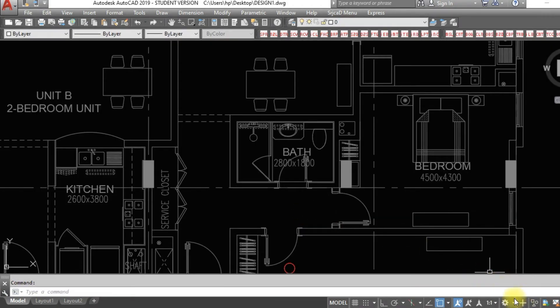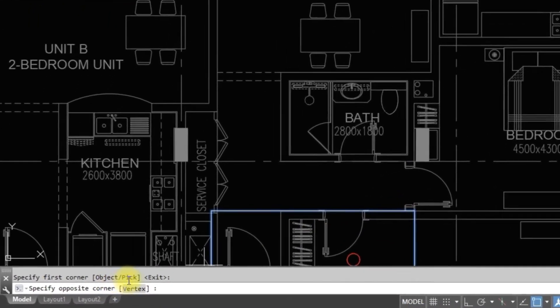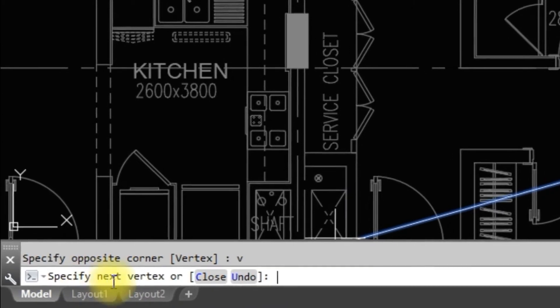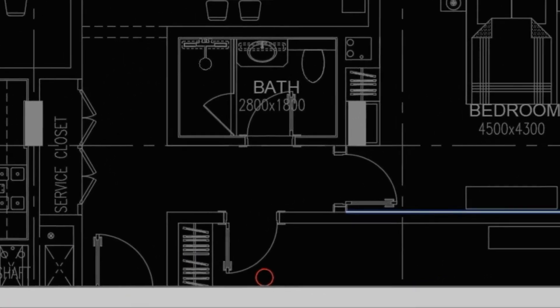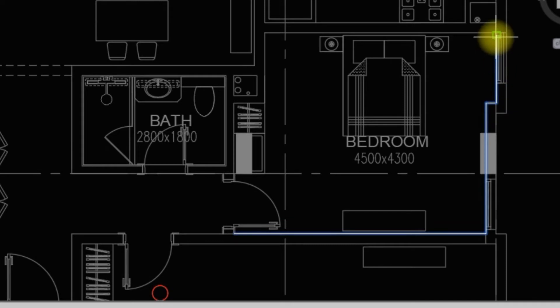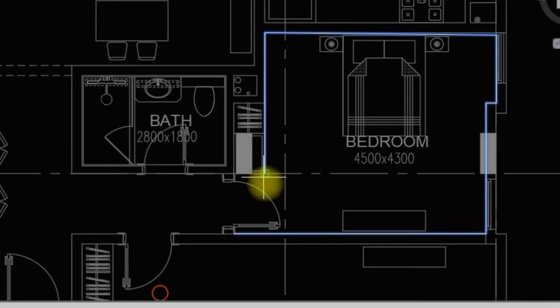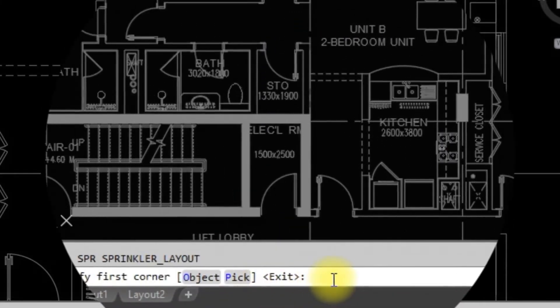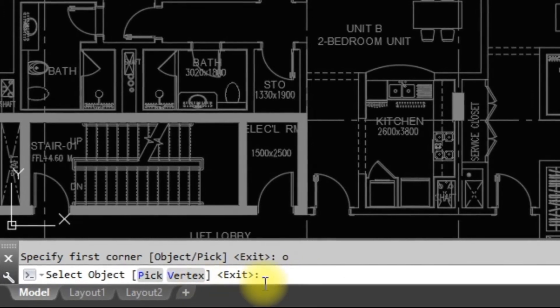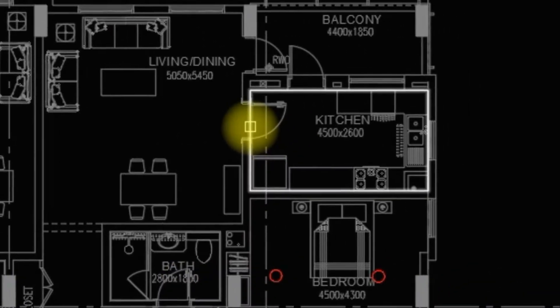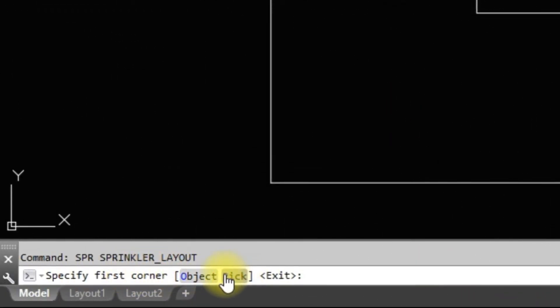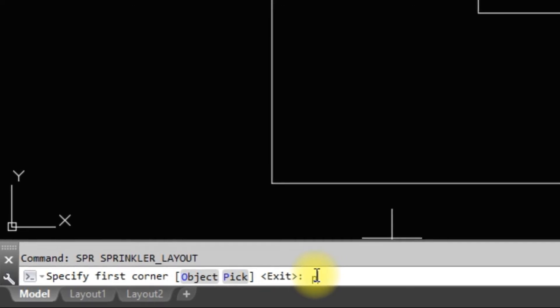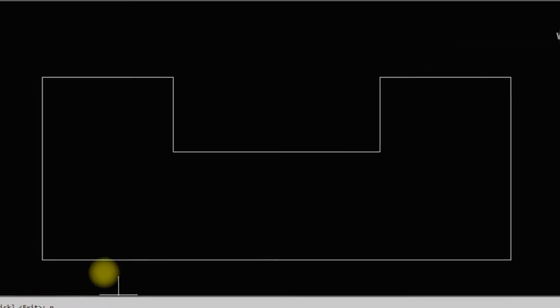The second type is by selecting a first corner and then selecting many vertex points. The third type is by selecting an object — select closed polylines to draw sprinklers inside them. The fourth type is by selecting a pick point. If an automatic boundary can be selected using pick points, sprinklers will be drawn inside it.